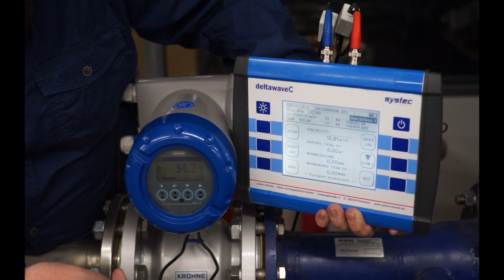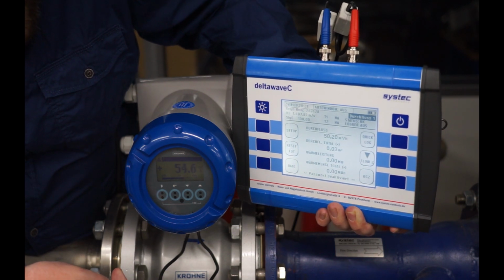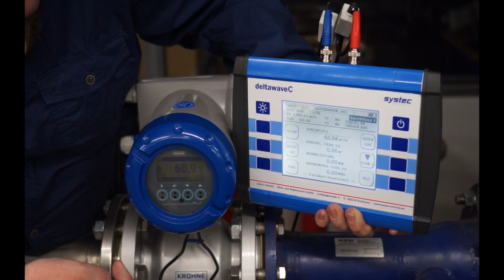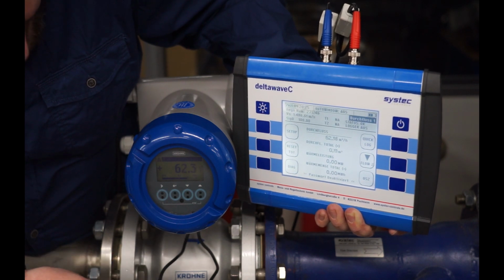As you can see, comparing the results to our hard-mounted equipment, the values for flow are very close between the inline flow meter and deltawaveC clamp-on flowmeter.